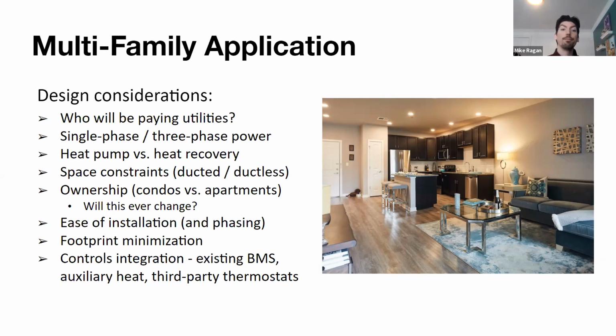Heat pump versus heat recovery. Are we going to want simultaneous heating and cooling throughout a space? Sometimes the question comes up: it's a multifamily apartment complex, and I would like to have all my tenants have the ability to independently choose heating and cooling, but maybe it's low-income housing and budgeting is an issue, and they don't quite have the finances for a heat recovery system that will allow for simultaneous heating and cooling. It's not a major buyout, but it is certainly a cost premium in the range of 15 to 20% to allow for that simultaneous heating and cooling. So that's a question that would certainly determine which direction we go.